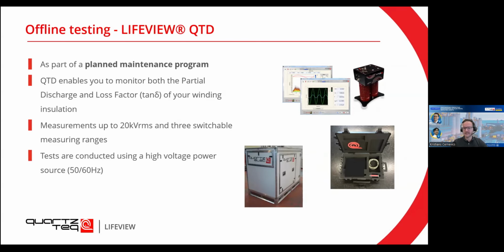As I mentioned previously, you would get a similar PD pattern. You would get, again, trend values to compare with the previous measurements. However, these PD patterns and maybe the magnitudes would be different from online because we're measuring slightly different conditions, mainly from the electrical stresses. But offline measurements give you a better possibility to pinpoint the location of the problem. So once again, both the online and offline solutions should be used complementarily.